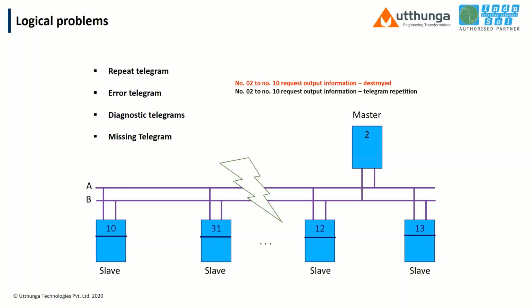Then what is an error telegram? Since Profibus is a process field bus system, it is completely in binary structure, 0, 1, 0, 1, like that the communication goes. If any parity bit error or delimiter error, some coding error comes in the network, this is an error telegram. Then what is a diagnostic telegram? A diagnostic telegram is dependent on the slaves. If slaves have an internal issue, like any loose contact or any IO device failure, slaves will give information to the master: I have an issue. Then missing telegram. What is a missing telegram? Like slave 10 is not giving data back to the master. That is a missing telegram. These are some logical parameters we have mentioned for Profibus networks.